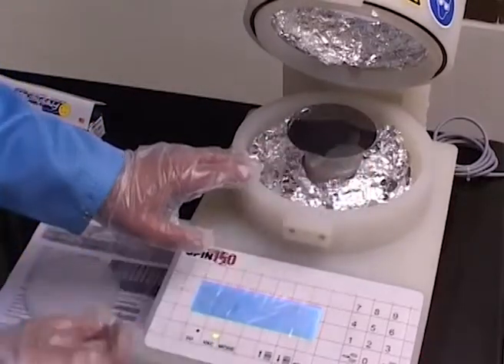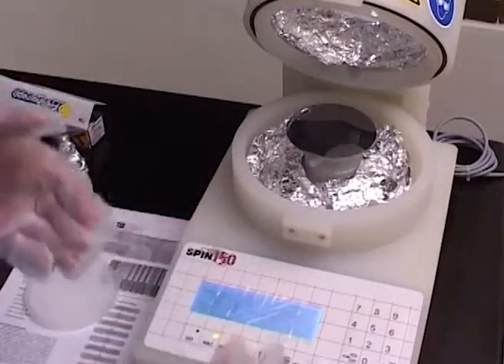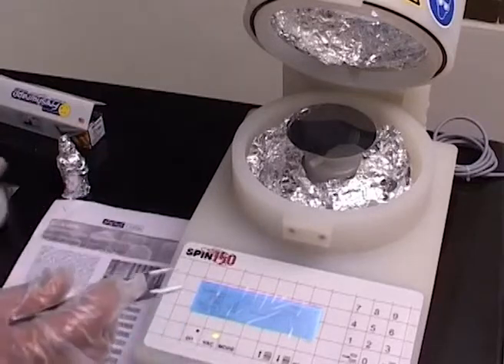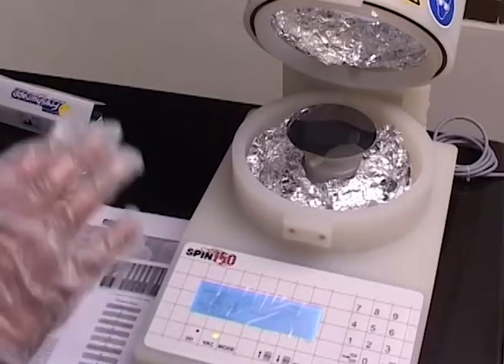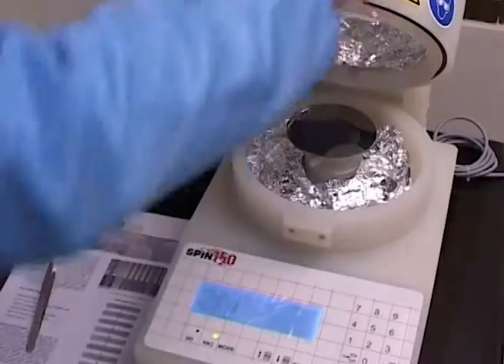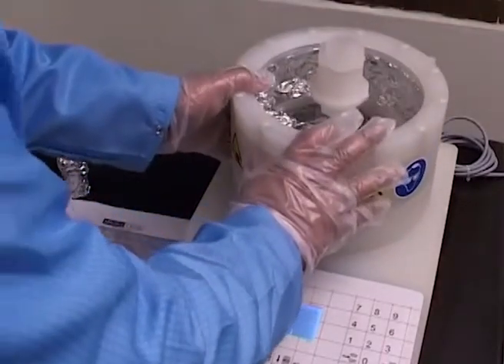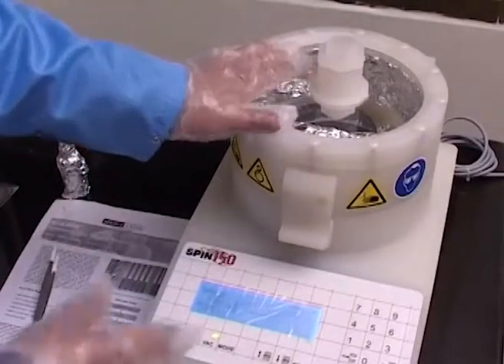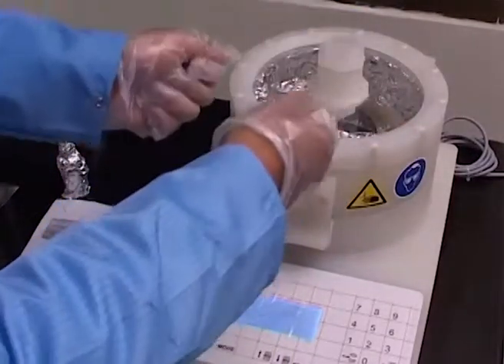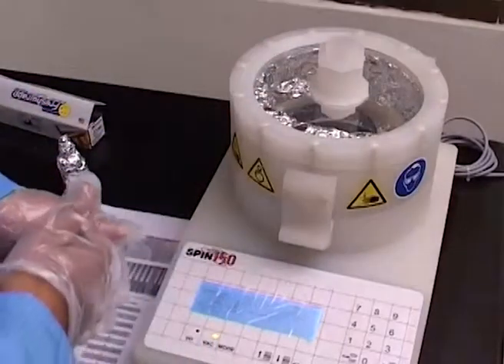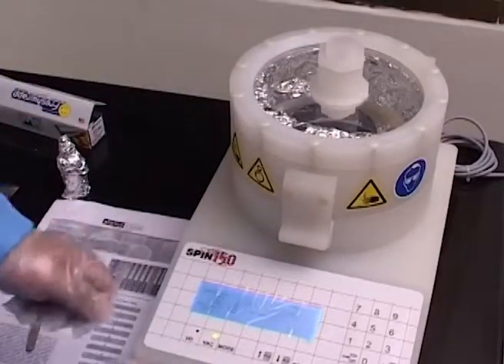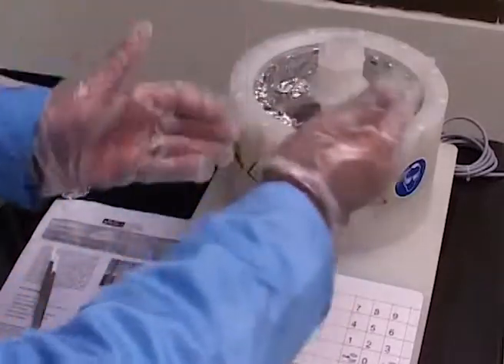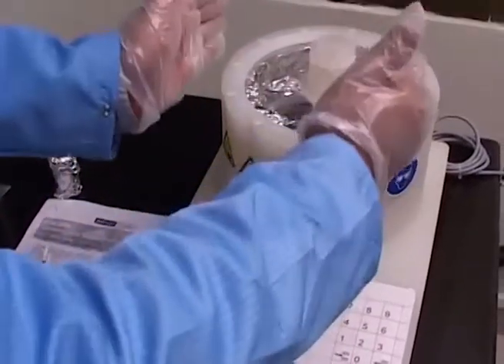Now it is almost ready to rotate and spin and coat whatever is there on the surface of the material. We would like to also have a look at whether this wafer has been centered, and the best way to do that is to close the lid and see from this transparent section on the top whether this wafer is really at the center of the spin table. In case it is not, then you can switch off the vacuum and change the position so that the wafer comes pretty much at the center of the spin table.